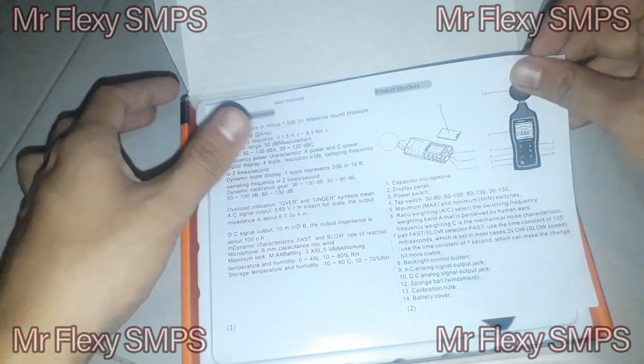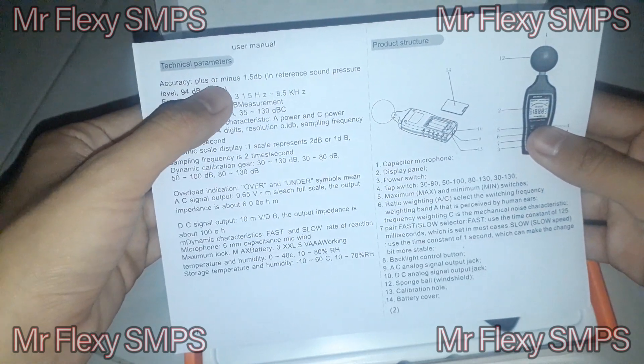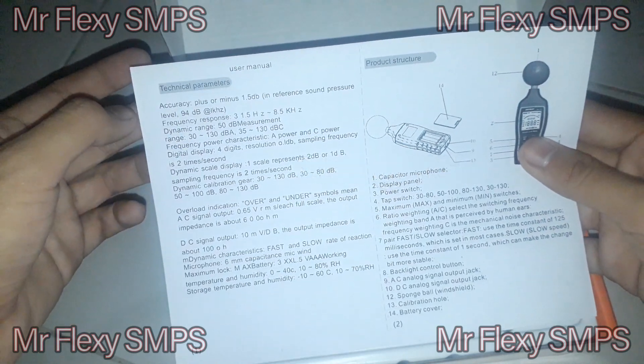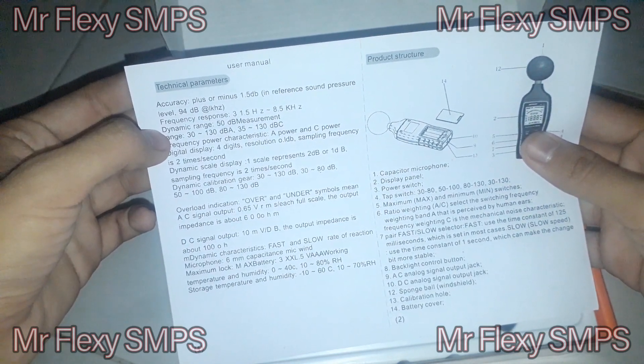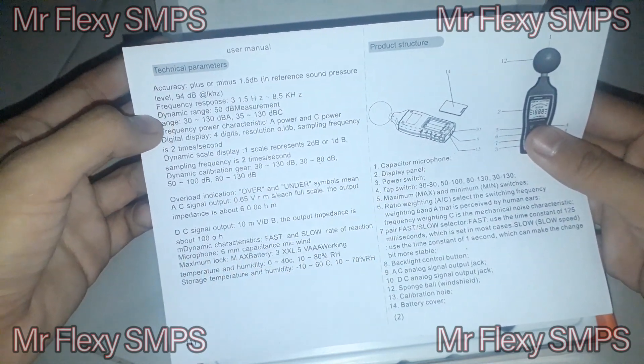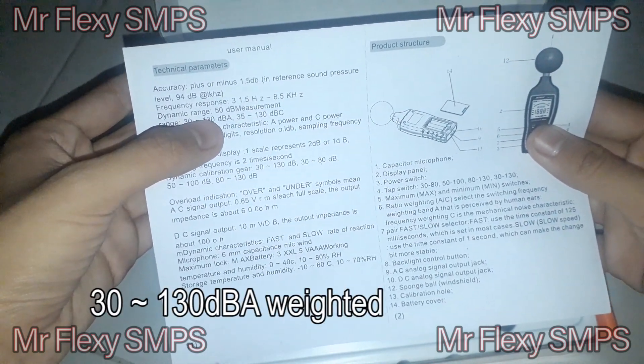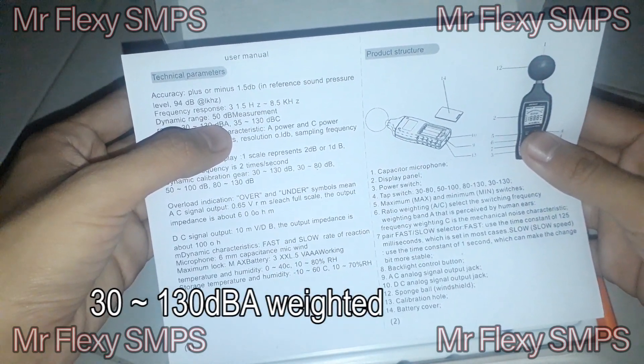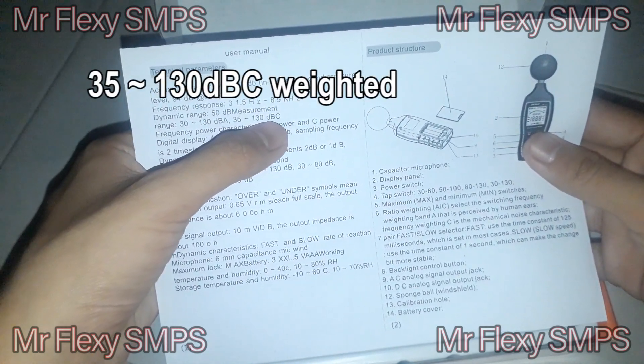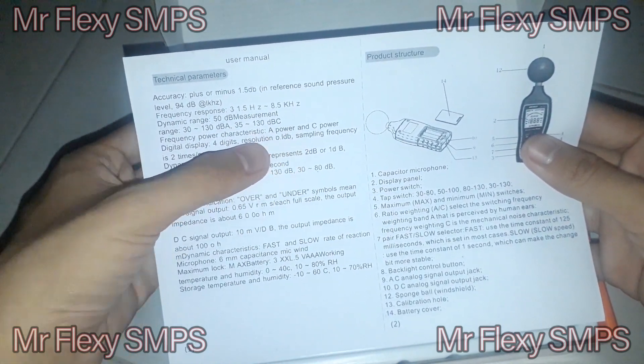We find some manuals. It has accuracy of about plus or minus 1.5 dB. The reference sound pressure level is 94 dB at 1 kHz. Frequency response is from about 31.5 Hz to 8.5 kHz. We have a dynamic range of 50 dB, measurement range from 30 to 130 dB A-weighted, and about 35 to 130 dB C-weighted. So we have frequency weighting characteristics: A-weighting and C-weighting.